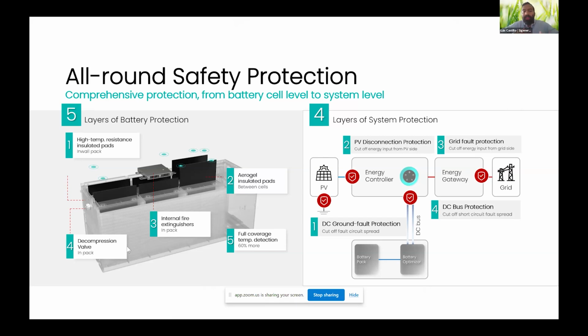If the temperature in one of the cells increases too much, we've added aerogel insulated pads between cells which slow down heat transfer. However, if the heat spreads around battery cells and the temperature inside the pack reaches dangerous levels, there is a dedicated fire extinguisher per pack that triggers if that target temperature is reached, cooling down the battery pack. At that point there might be an increase in pressure due to the temperature, so there's an automatic decompression valve to relieve that pressure. There's also a high temperature resistant insulating pad around the whole battery pack that contains any high temperatures and makes the pack safe to change.